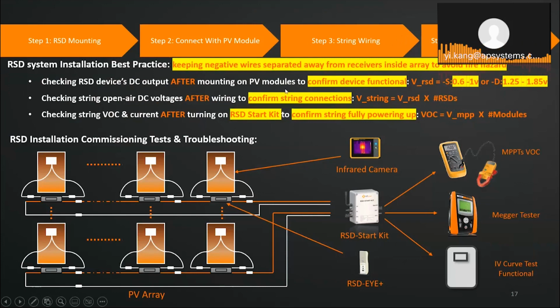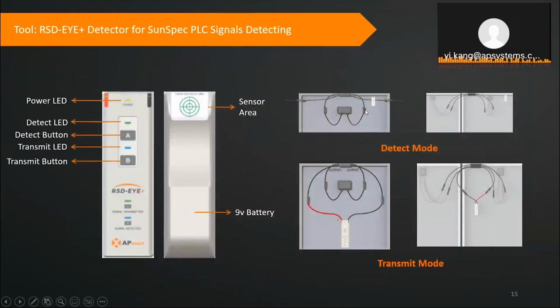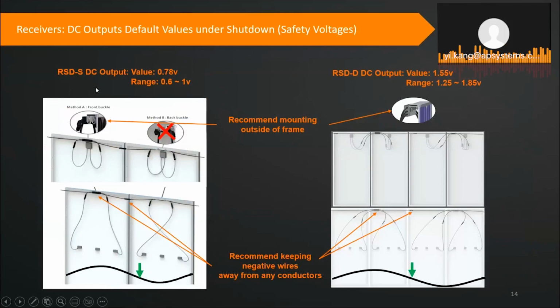After the best practice, for each device, sorry, I didn't mention this one. For the single, when you connect it with a panel, the DC side power will turn on this device. There is no power and no current output, but there is what we call a safety voltage. It's about 0.78 volt on average, but it's a range. It's above 0.6 but below 1 volt. Keep in mind that this number is very important.